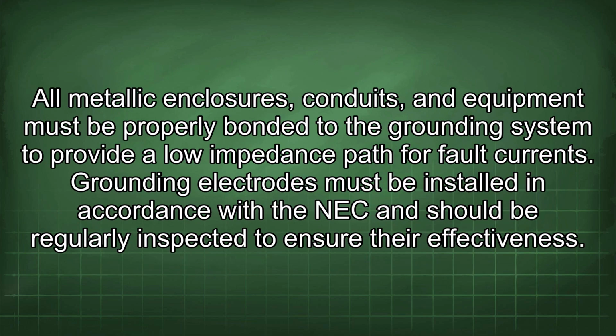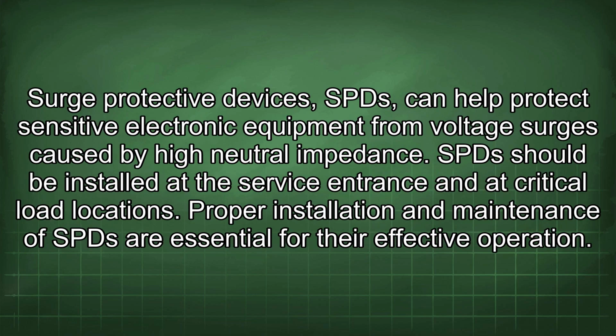All metallic enclosures, conduits, and equipment must be properly bonded to the grounding system to provide a low impedance path for fault currents. Grounding electrodes must be installed in accordance with the NEC and should be regularly inspected to ensure their effectiveness. Surge protective devices, SPDs, can help protect sensitive electronic equipment from voltage surges caused by high neutral impedance. SPDs should be installed at the service entrance and at critical load locations. Proper installation and maintenance of SPDs are essential for their effective operation.